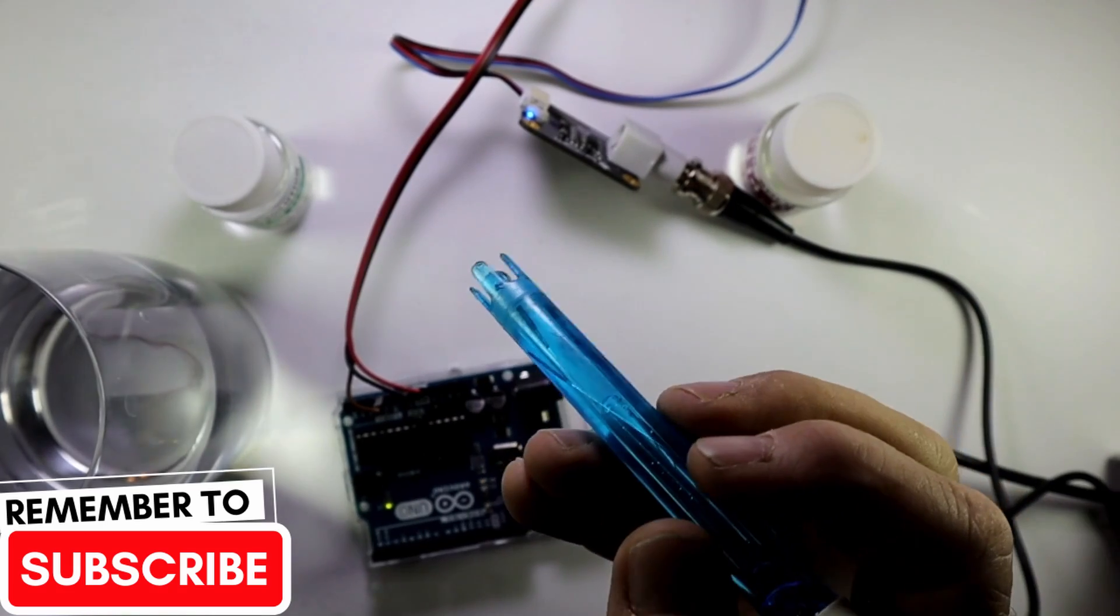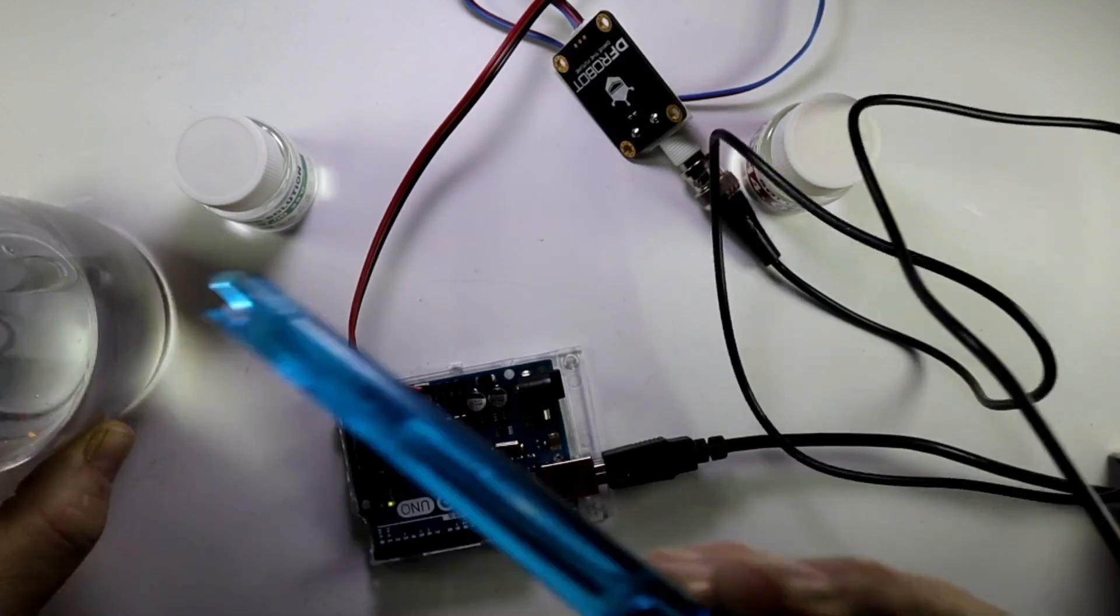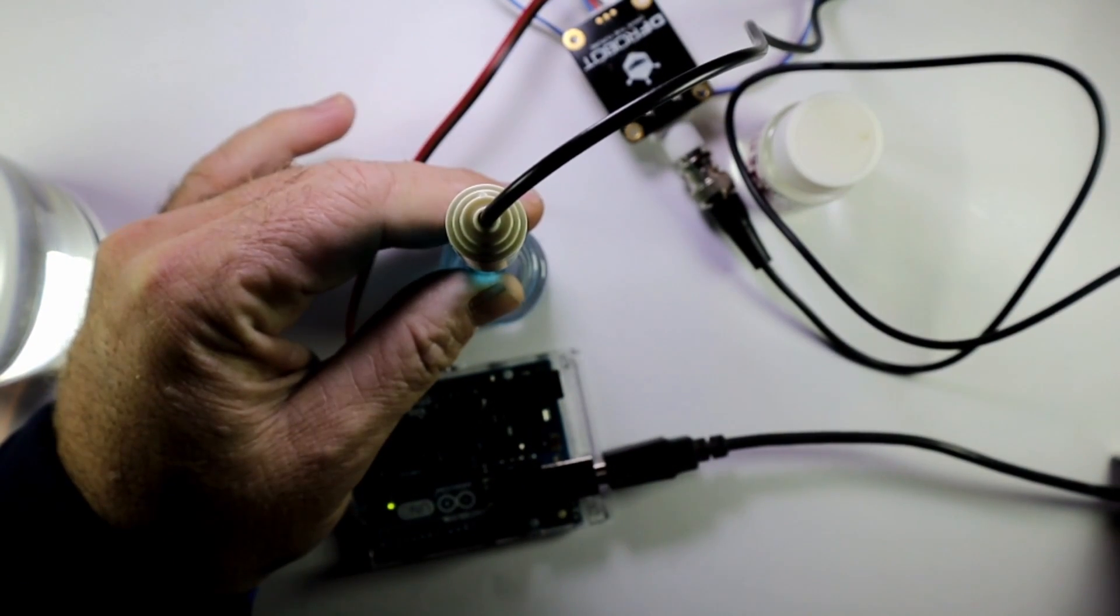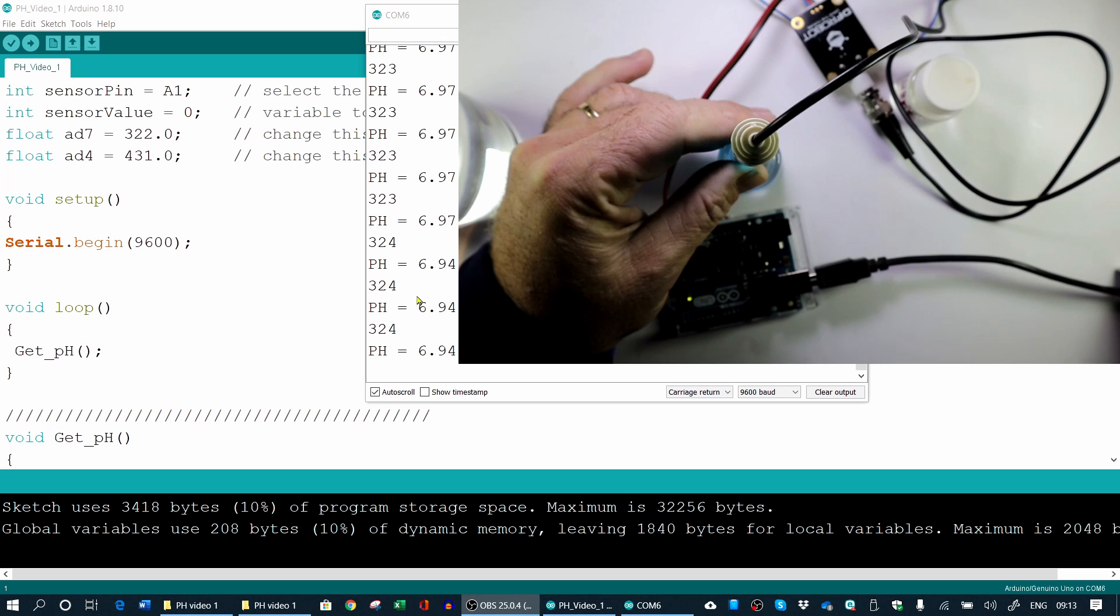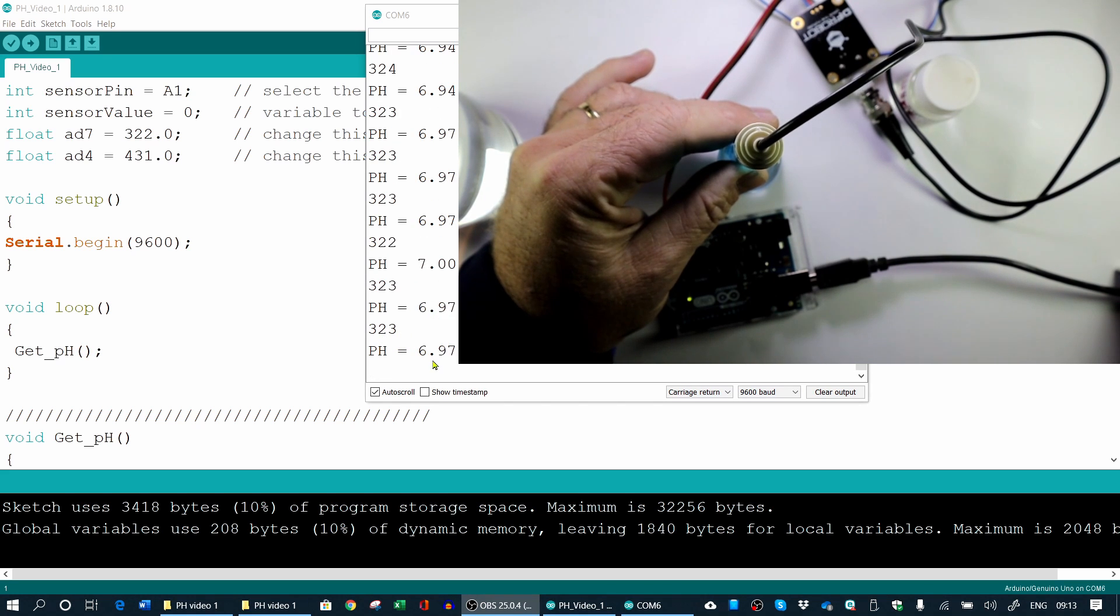Then you rinse your probe in clean water. Shake it off a little bit. Then we can take our seven buffer. And we put our probe in there. And I'm just going to hold it there. So now you can still see. You can see the measurements going on. So it's supposed to be seven at the moment. So I'm going to change my value now. There you can see it's seven.